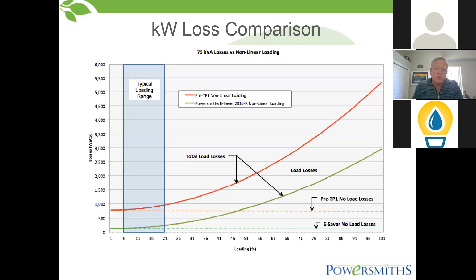I bet you it's no more than 20% loaded. And they go, no way. Why is it so hot? I said, because of the losses there. Think about it: you've got a 75 kVA transformer with 700 watts of no-load losses, and with loading it's probably 1,000 watts. It's like having a hair dryer on 24/7, 365, just sitting there cooking. So a hair dryer sitting there for a long time is going to be hot inside of a metal case. So it's going to be hot. It is what it is.